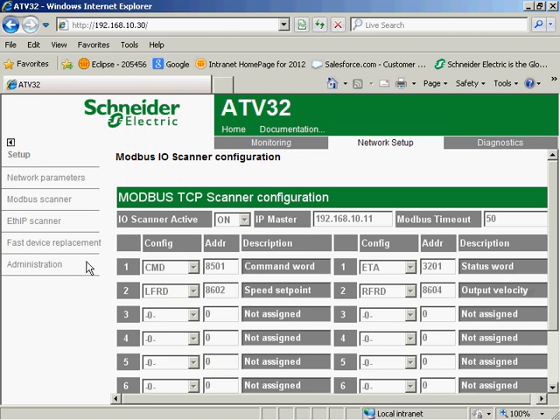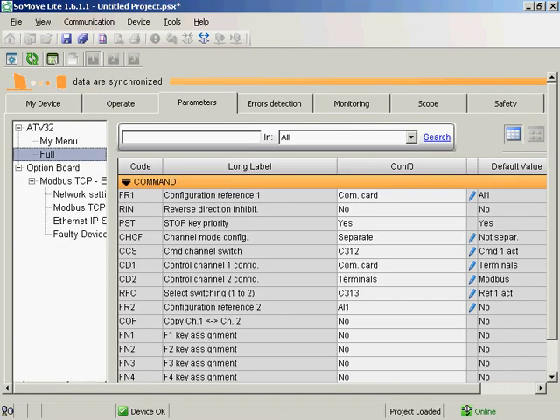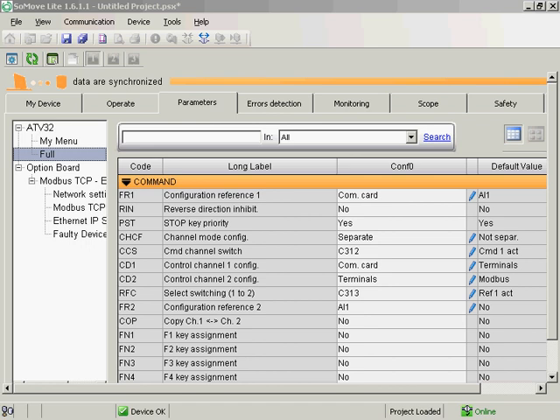So, the third way we can set the drive up is using our SoMove software. SoMove is quite easy to use. And again, I'm just going through the software pertaining to the communication setups. So, if I go to the full menu, the command, I have the channel mode configuration. I've got that set for separate.